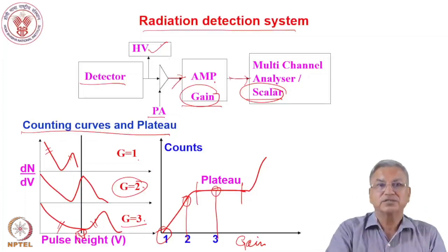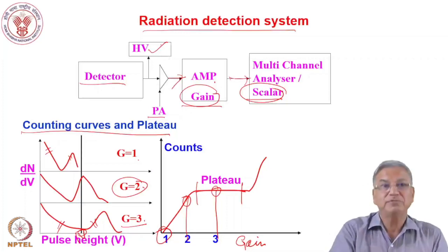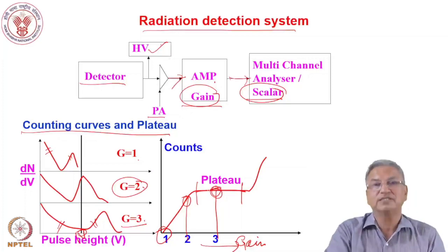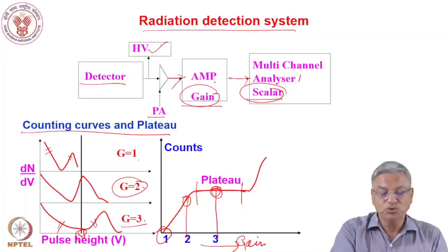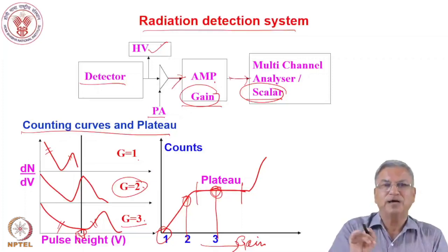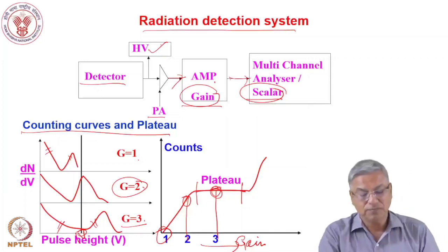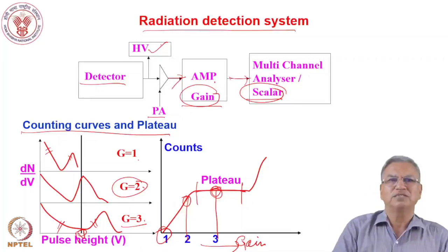In detectors like the Geiger-Müller counter, you can change the gain of the detector system by the high voltage itself. In the GM counter, instead of gain you change the high voltage and find the voltage at which the detector system is stable. Counting curves and plateaus are routinely used in the GM counter to set up the high voltage so the detector system functions properly and gives reliable, stable results.